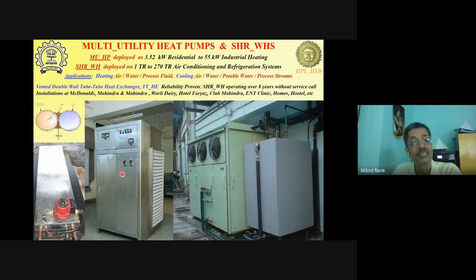In this case, we are eliminating those complexities, we are simplifying the system, we are reducing the cost of the system, and overall the system controls and everything becomes much simpler. And because the system is simple, it is also likely to be more reliable. And so our reliability was also proven to be very, very high. The other options where we use these types of heat exchangers are for systems for concurrently cooling air, cooling water, cooling potable water, and cooling process streams directly.